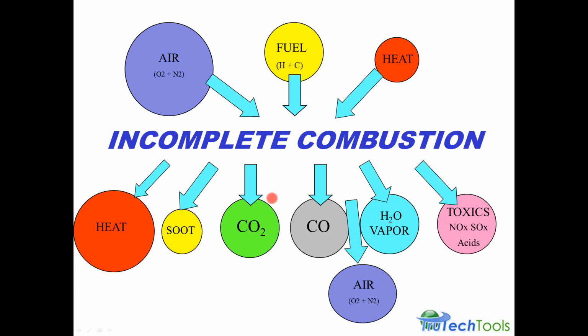Soot is another product of incomplete combustion, and you may be more familiar with that if you're using or testing oil burners. That would be the smoke spot test, which would show up as soot. The smoke comes from raw carbon particles from the fuel that never even combust at all with air, never make it even partway to CO, let alone to CO2. Just raw carbon particles are being moved through the process and coming up as soot, so that's carbon.